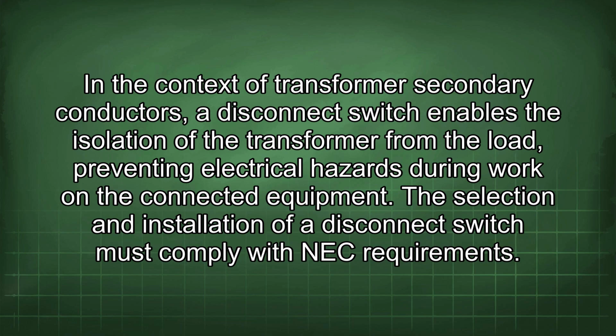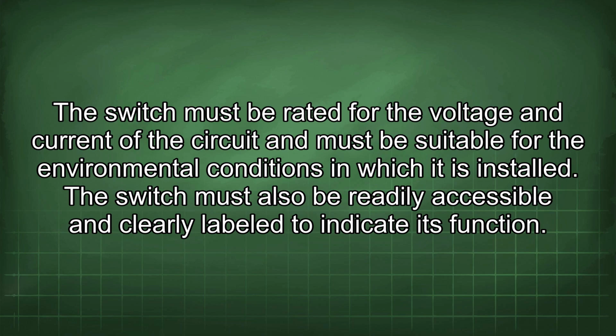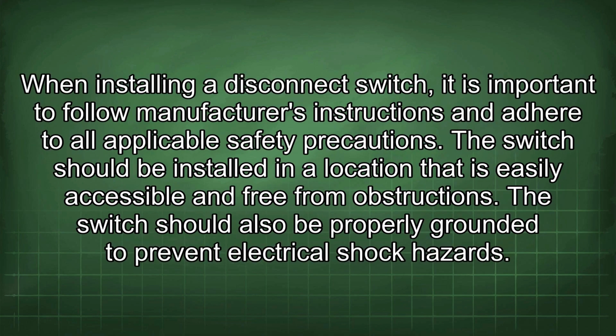The selection and installation of a disconnect switch must comply with NEC requirements. The switch must be rated for the voltage and current of the circuit and must be suitable for the environmental conditions in which it is installed. The switch must also be readily accessible and clearly labeled to indicate its function. When installing a disconnect switch, it is important to follow the manufacturer's instructions and adhere to all applicable safety precautions. The switch should be installed in a location that is easily accessible and free from obstructions. The switch should also be properly grounded to prevent electrical shock hazards.